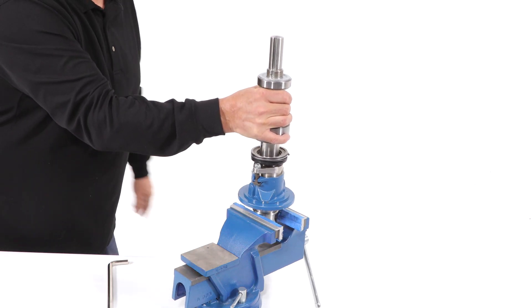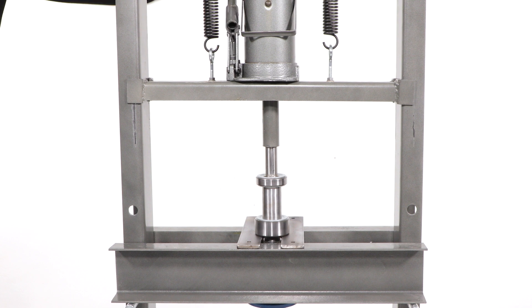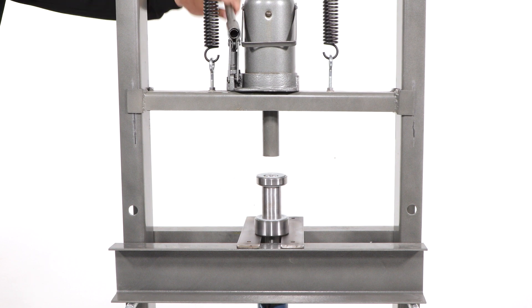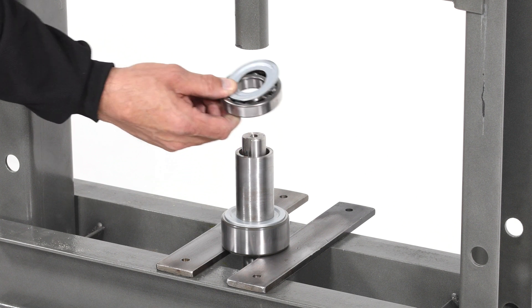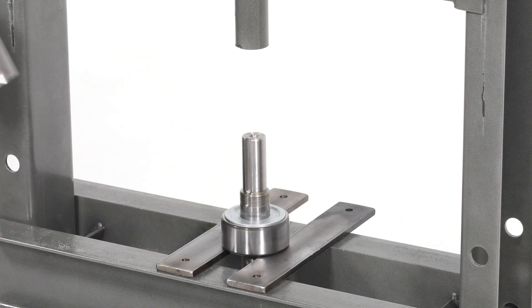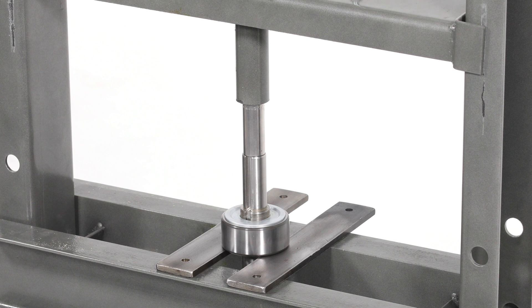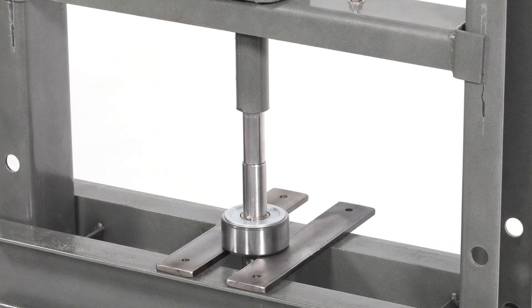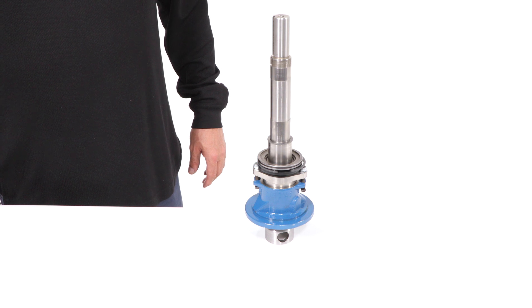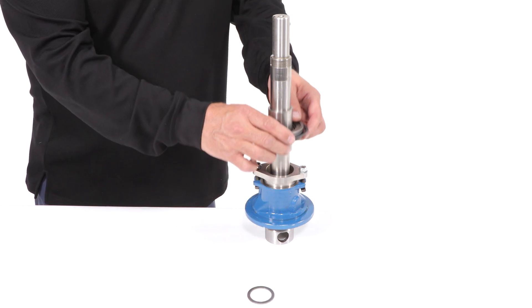The bearings will be removed from the shaft with a press. Center the drive shaft assembly as shown, pressing the inner race of the axial bearings to remove both bearings. Slowly press the drive shaft until it falls. Remove the grease shield, top bearing, and shaft sleeve before pressing further. Continue to press the drive shaft until the second bearing is removed. Remove the spacer, followed by the shaft sleeve, bearing cover, snap ring, and flinger ring.